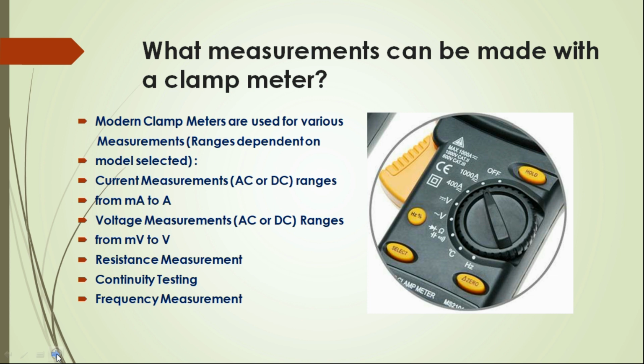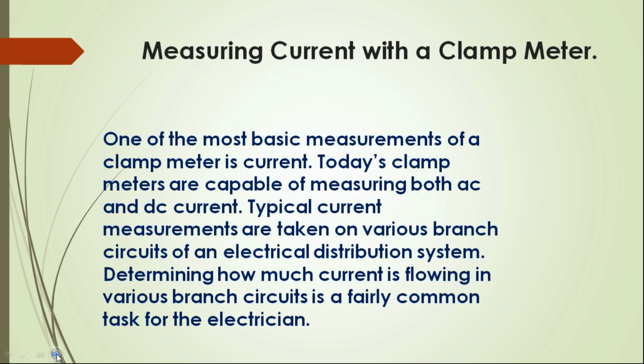Now, measuring current with a clamp meter. One of the most basic measurements of a clamp meter is current. Today's clamp meters are capable of measuring both AC and DC current. Typical current measurements are taken on various branches of circuit of an electrical distribution system. Determining how much current is flowing in various branch circuits is a fairly common task for the electrician.